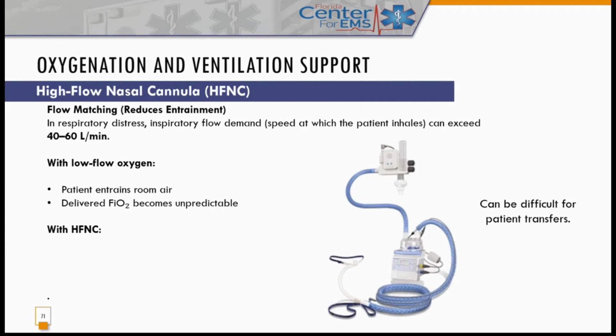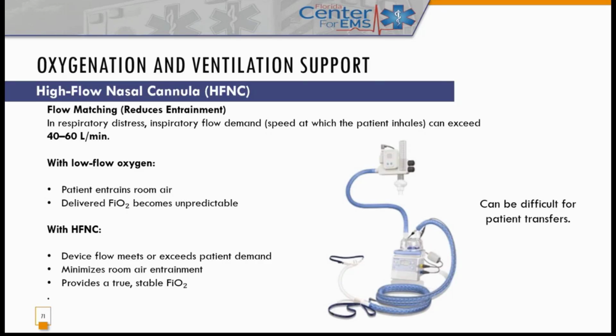That's what I would recommend to any transport unit, unless they have a setup where they have either a compressor or a medical air tank. Routine ambulance transports or rescue transports don't have that. But with this device, you could actually do it. So the device flow meets or exceeds the patient's demand. Remember I talked about the peak inspiratory flow? If you're starting out with 60 liters, you're going to be right there.